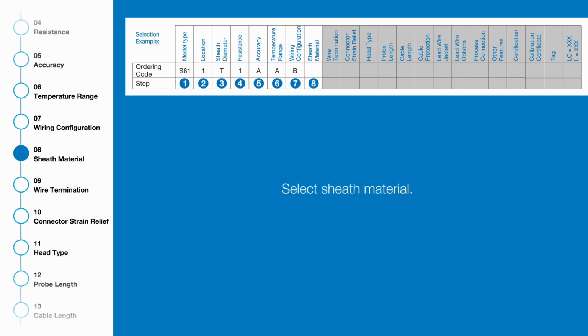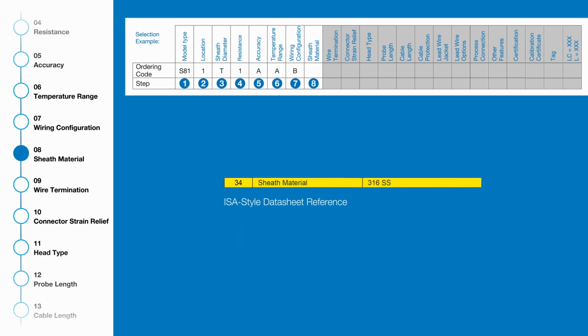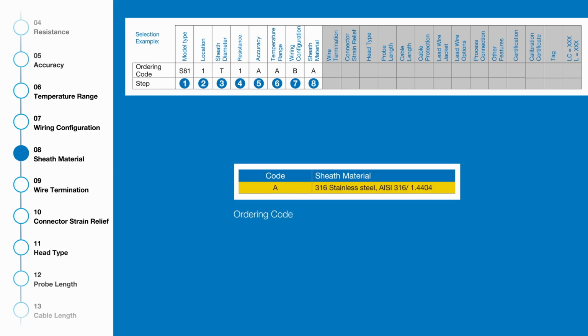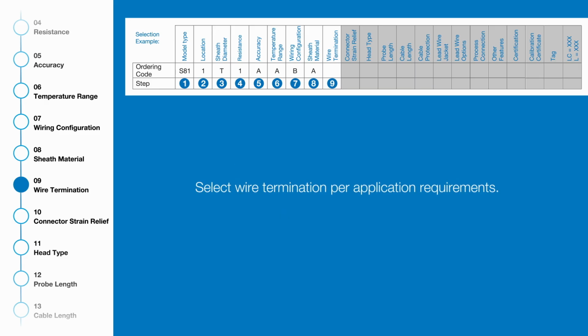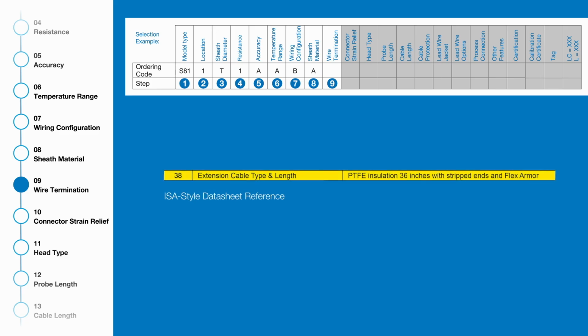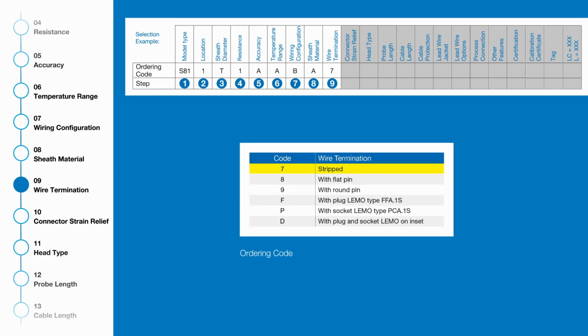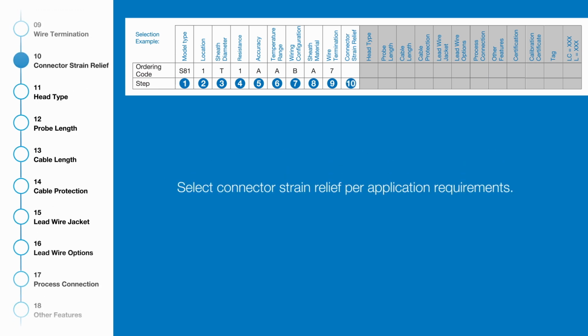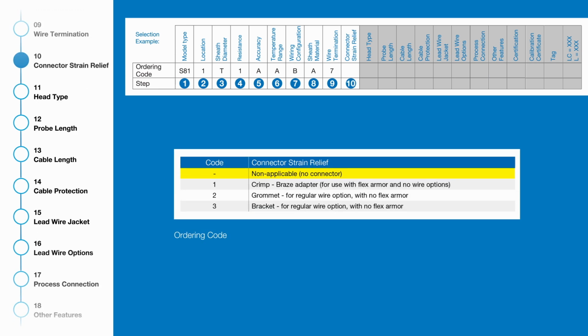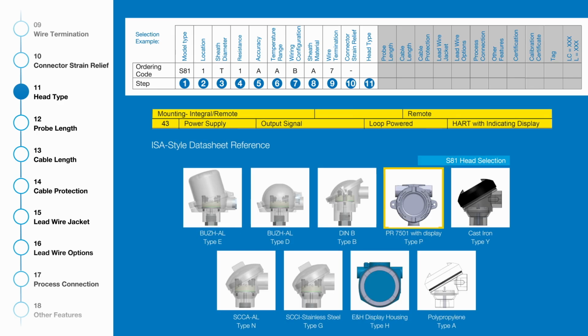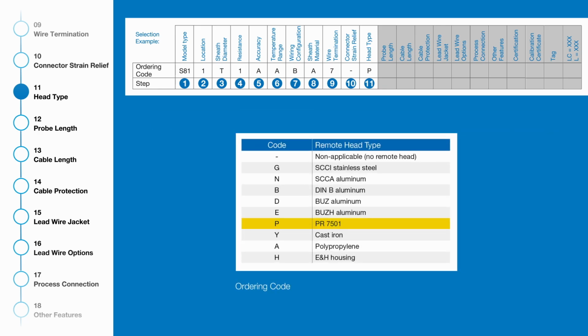Sheath material requirement is for 316 stainless steel. We're going to select code A. For wire termination, it was stripped ends, so we're going to select code 7. For the connector strain relief, there was no requirement, so we're going to select dash. For the head type, there is a requirement here. This is going to be a remote head with the transmitter with display. For this, we're going to select code P, the PR7501.